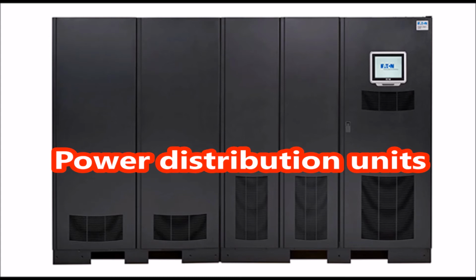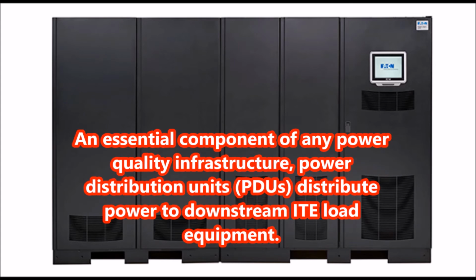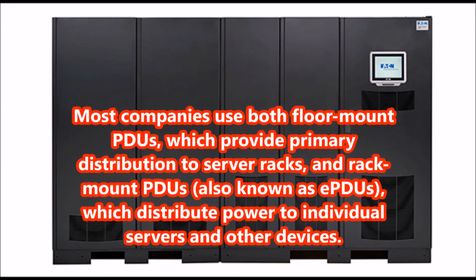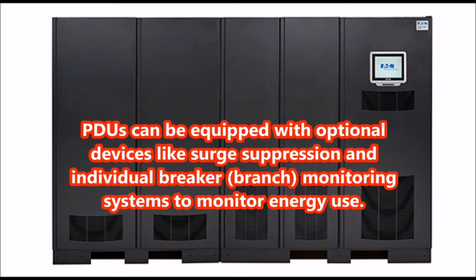Power distribution units. An essential component of any power quality infrastructure, power distribution units (PDUs) distribute power to downstream IT load equipment. Most companies use both floor-mount PDUs, which provide primary distribution to server racks, and rack-mount PDUs, also known as ePDUs, which distribute power to individual servers and other devices. PDUs can be equipped with optional devices like surge suppression and individual breakers, and branch monitoring systems to monitor energy use.